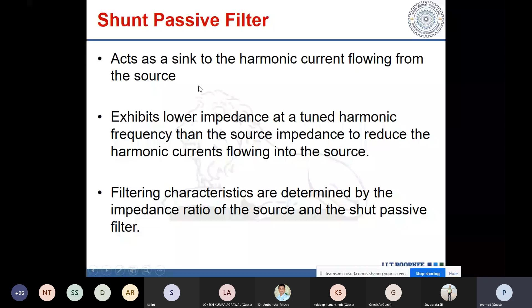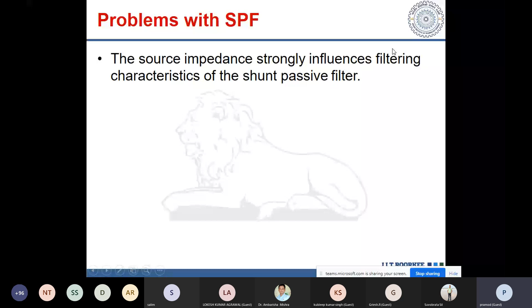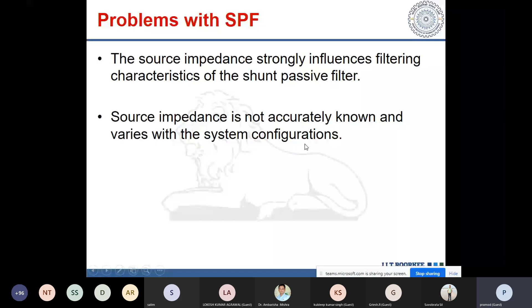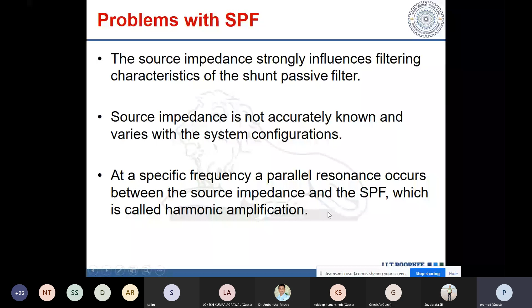So the filtering characteristic of this passive filter is affected because the source impedance keeps on changing. Source impedance strongly influences the filtering characteristic, is not known, and varies with the system configuration. Then there is frequency variation, and one more problem is resonance, which increases the harmonic component.